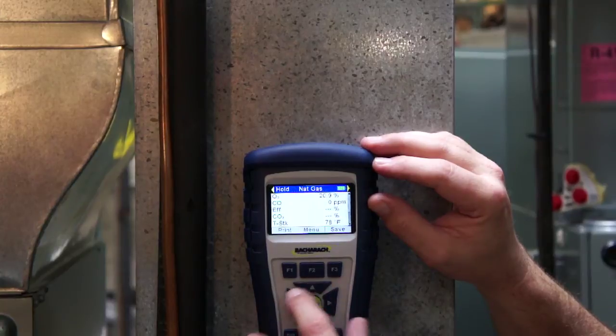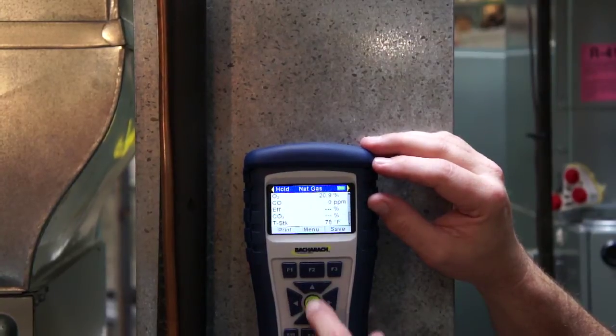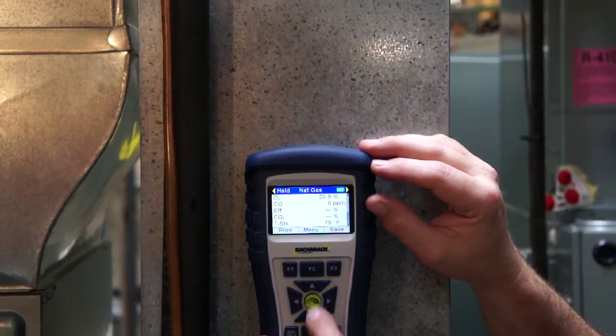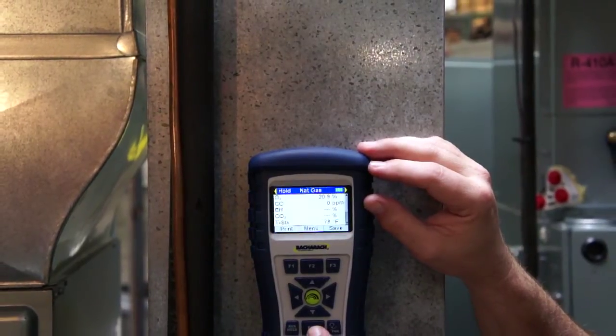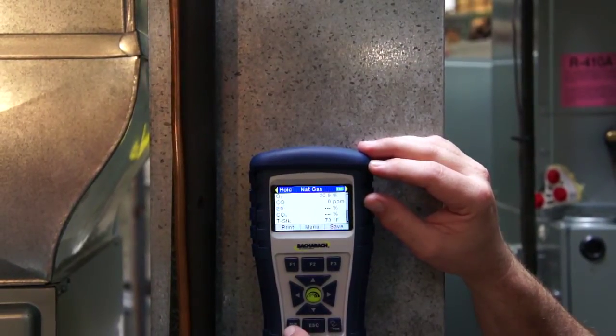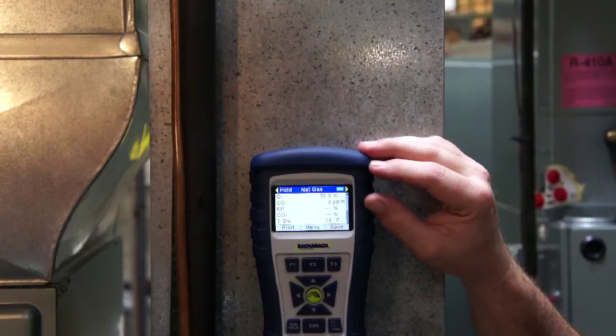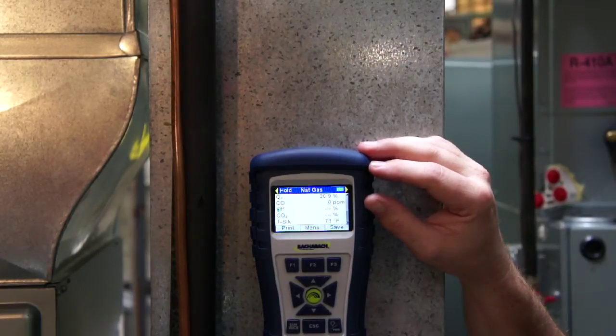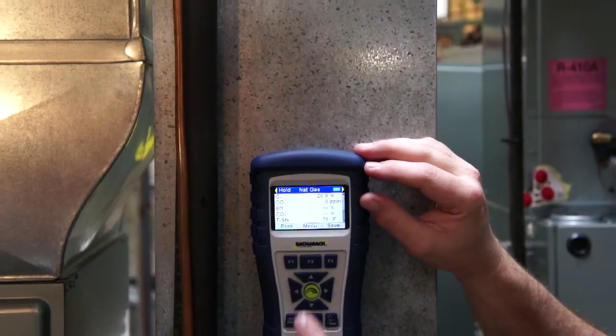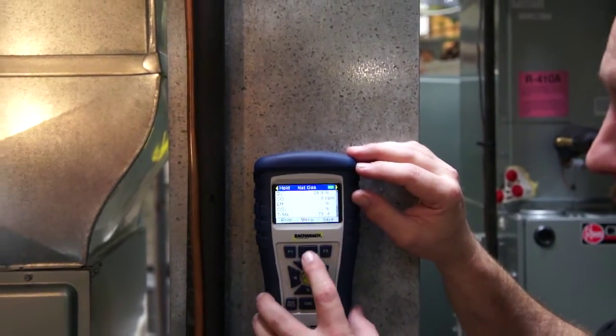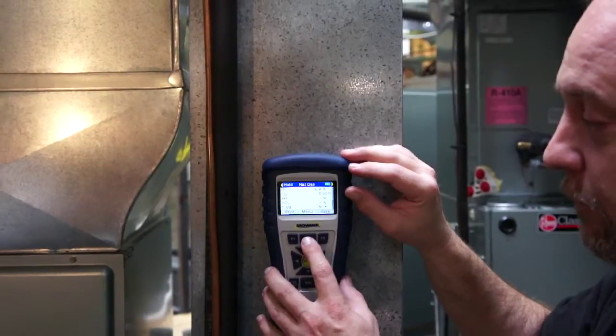Once you enter here, you have keys for left and right, up and down, and the center key is your enter key. You have your escape key, which moves you up and down in your menus, and then your run hold key, which will bring you back into your measurement menus after you've made any changes. One of the most important things I think on the instrument that you need to initially configure is the post-purge period on there, because it comes set to factory default to none.